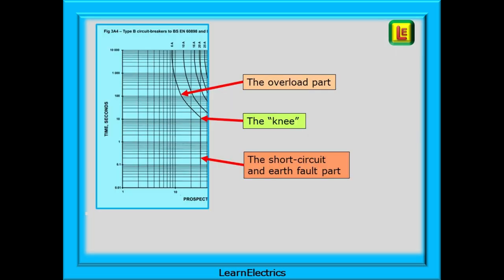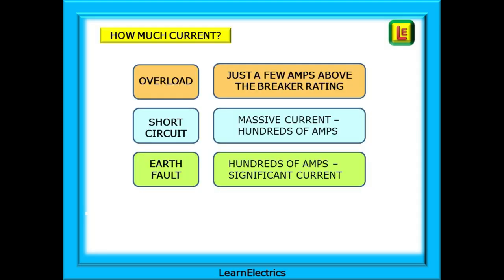Looking at an actual curve again we can see the curved overload part for a slow response. We can see the knee that divides the graph into two, and we have the short circuit part and the earth fault part that are the vertical line of instant tripping. Just to remind ourselves of how much current the different overcurrents will have, an overload is just a few amps above the breaker or fuse rating. Not a lot and it gets a slow response. Short circuit and earth fault currents are very high currents, hundreds of amps, and they have an instant response.